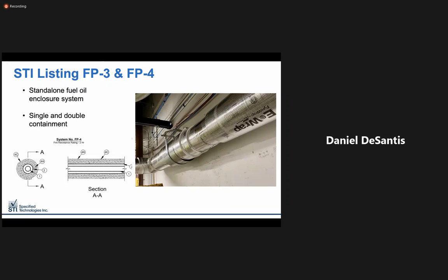On the fuel oil side, UL listing numbers FP3 and FP4 are STI's proprietary listing for fuel oil line enclosure. FP3 is used for single containment fuel oil line, whereas FP4 is used for double containment. When properly installed, these systems provide a standalone 2-hour rated enclosure under the UL 1489 test standard.